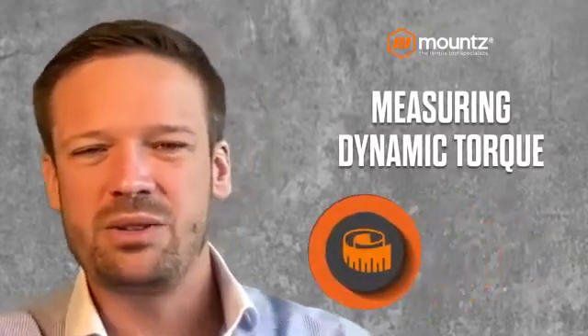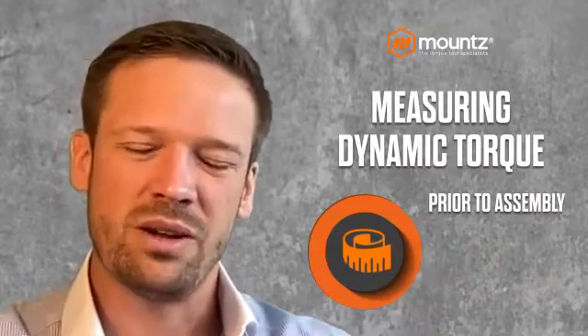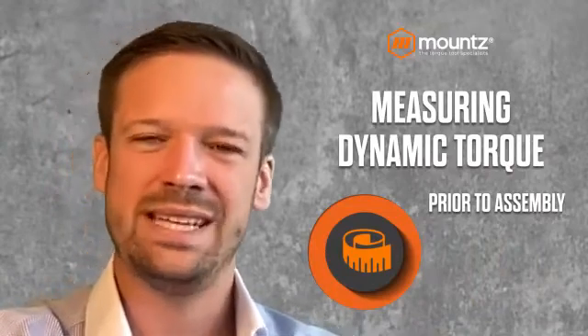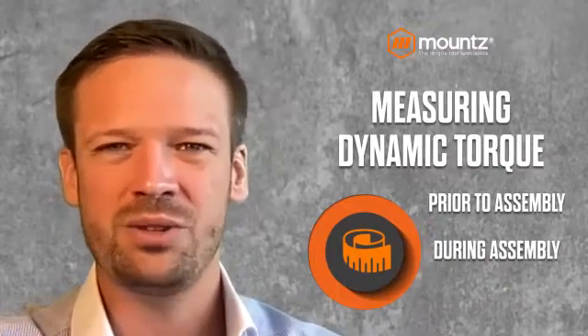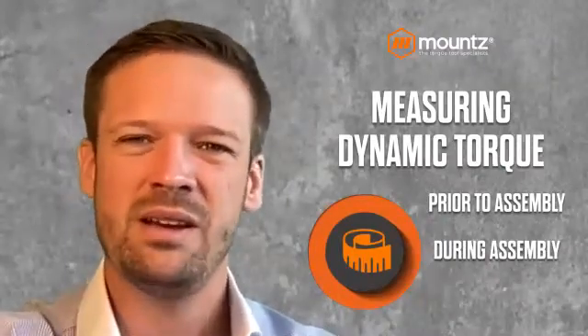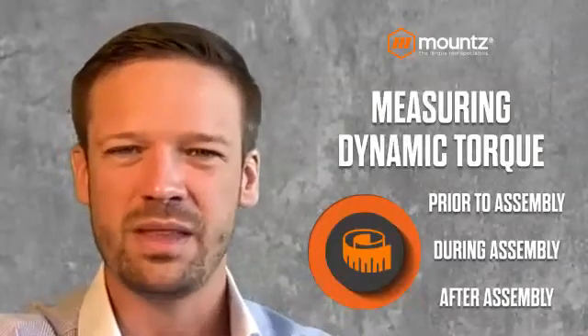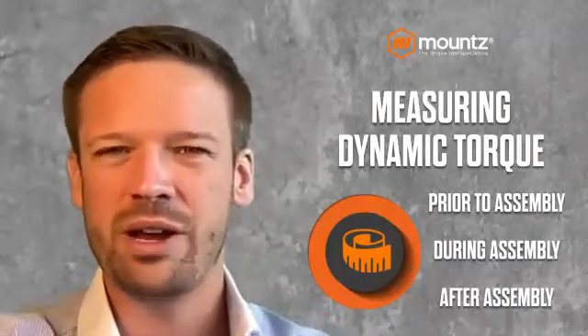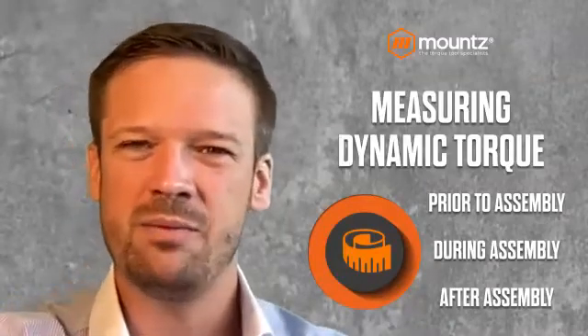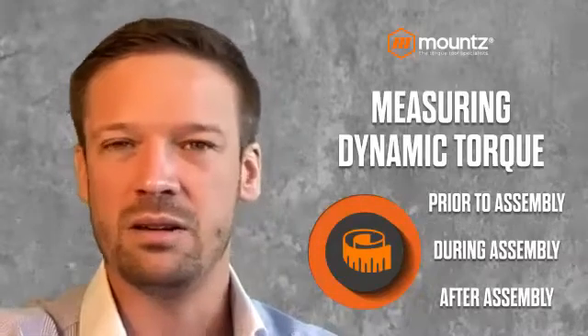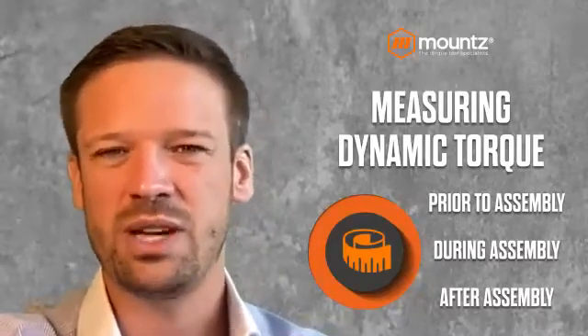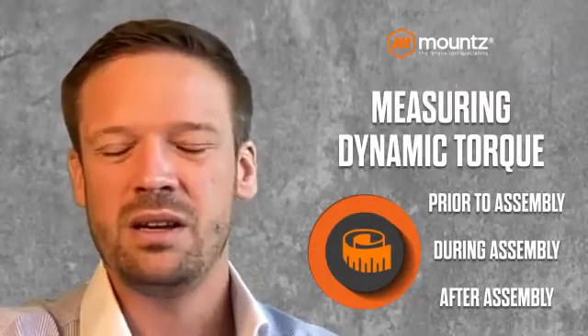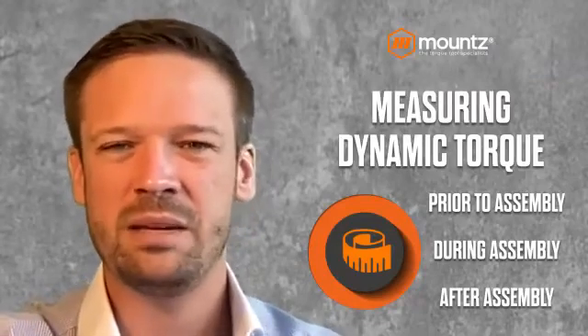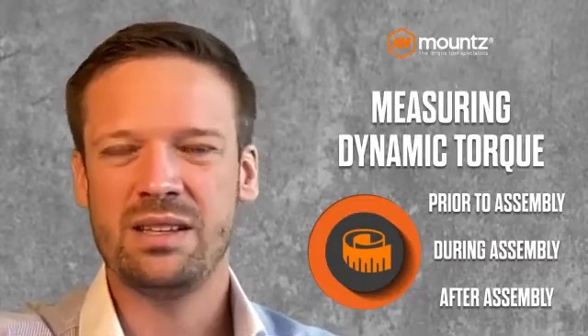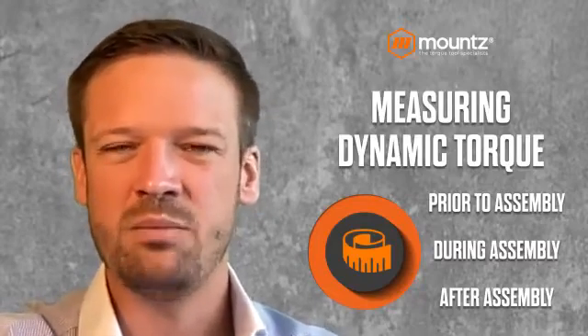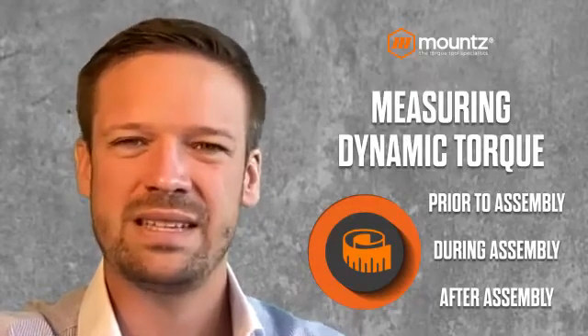Measuring with a dynamic torque sensor can be done around three phases related to the assembly. It can be done prior to the assembly, during the assembly, or after the assembly. If we do it prior to the assembly, this generally happens in a laboratory or dedicated space to check the tools. In this case, we need the sensor mounted on the rundown adapters so that we simulate the assembly. We then calibrate and check the tool before sending it to production.